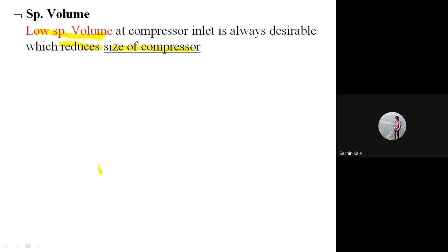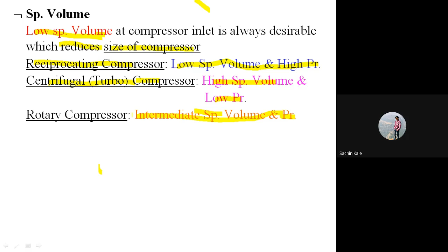Different types of compressors will be used depending upon the specific volume. If your refrigerant has low specific volume and high pressure, then we have to use the reciprocating compressor in a VCRS system. If your refrigerant has high specific volume and low pressure, then you have to choose the centrifugal, also called turbo type, compressor. And if your refrigerant has intermediate specific volume and pressure, then you have to select the rotary compressor. So the type of compressor we select for designing a VCRS system depends upon the specific volume as well as pressure of that refrigerant. Are you getting? So this is related to specific volume.